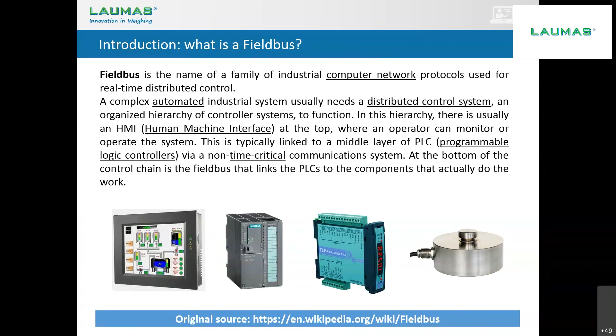Well, take note that all that we will show you and explain you during this presentation about Fieldbus is just referred to the weighing world and in particular to our specific experience, because we haven't a shared database with our competitors. What we can say for sure is that in the past, the main part of the connection between load cells and PLC were made via analog signal, so amplifying the millivolts coming from a load cell to 0 to 10 volts or 4 to 20 milliamps, for example.